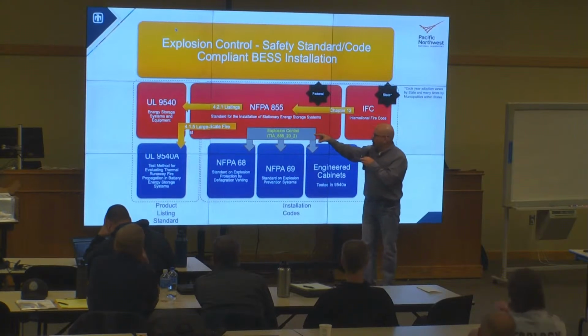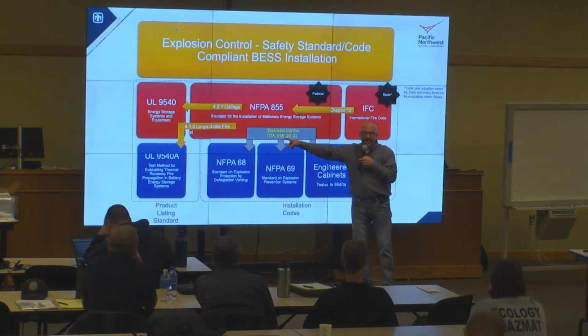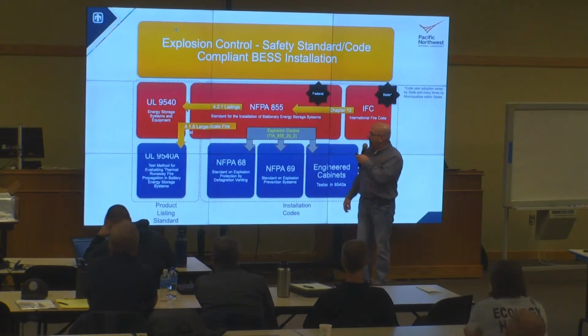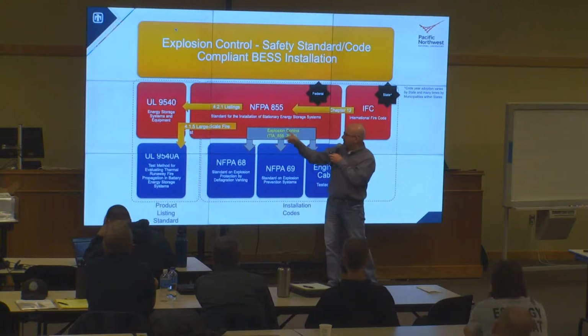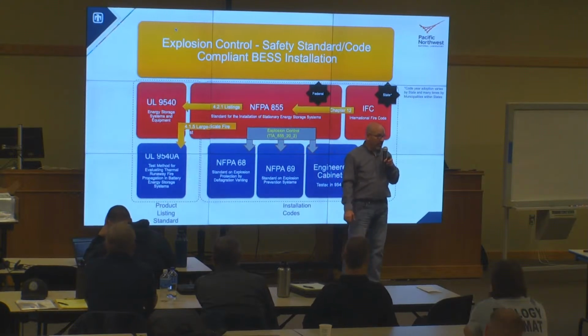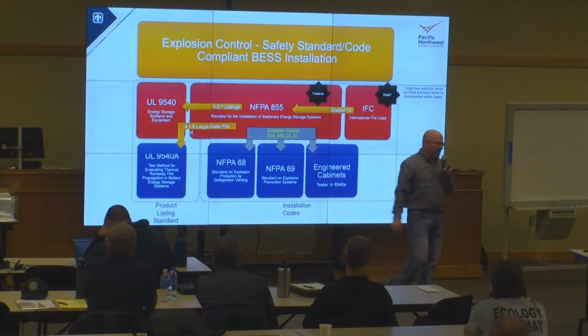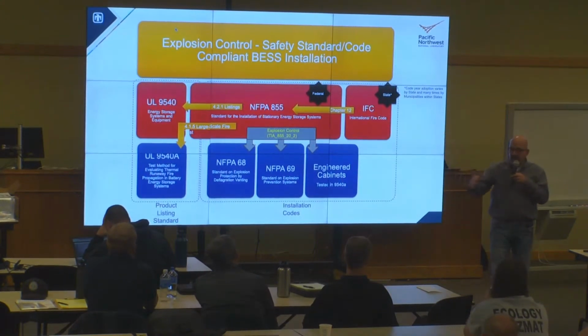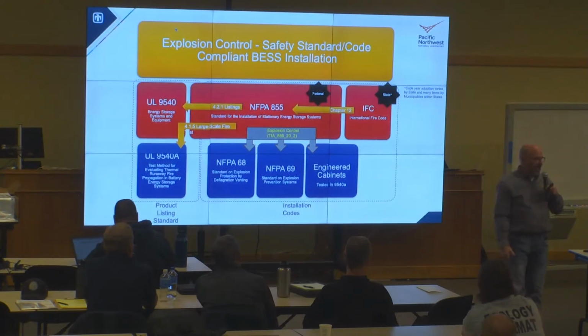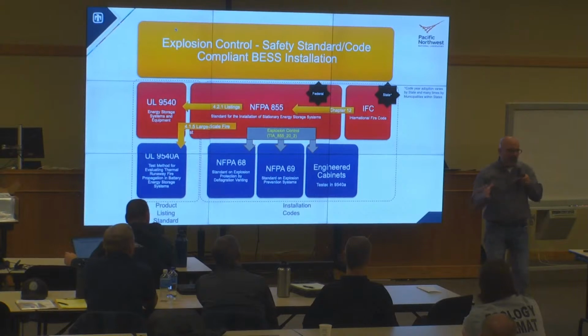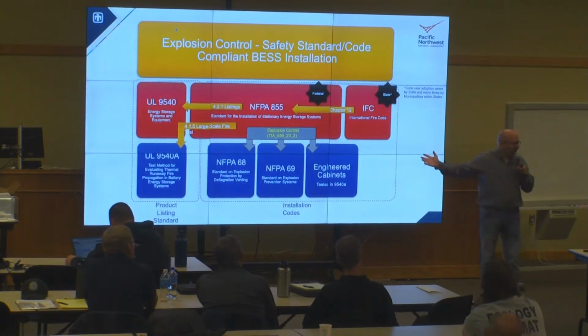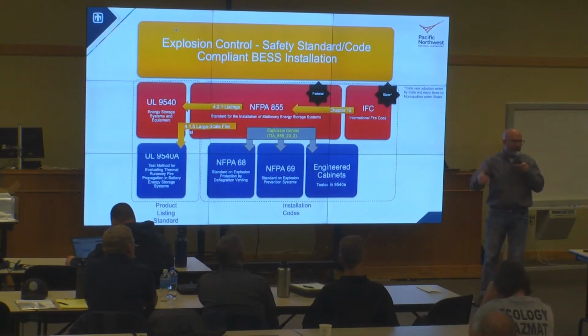For explosion control, there was a TIA, a tentative interim amendment, which is a change in the code, issued stating that the explosion control requirement applied to cabinets too. A lot of manufacturers, when they first started making these big energy storage systems, were putting them in shipping containers, Conex boxes, with a man door and an aisle and batteries on either side. Well, manufacturers started making them in cabinets, and a cabinet means there's no man door. You can't go inside it. Everything's accessible from exterior doors. Because the word cabinet wasn't included in a lot of sections of the code, they thought it doesn't apply to us, we've got a cabinet. So we went back and said, nope, cabinet applies for explosion control.